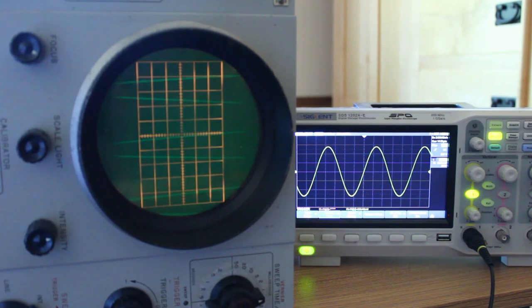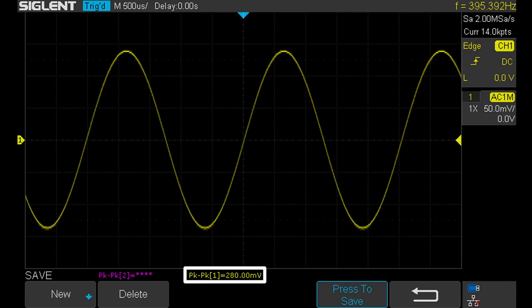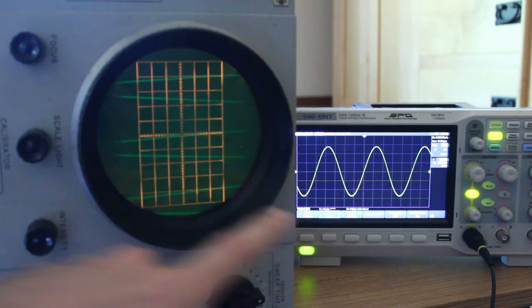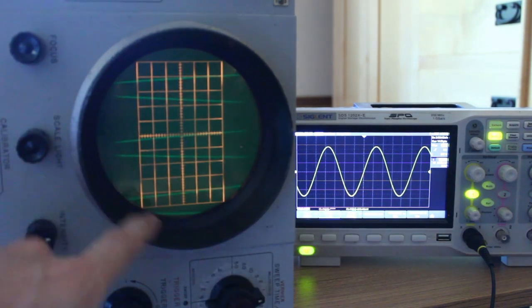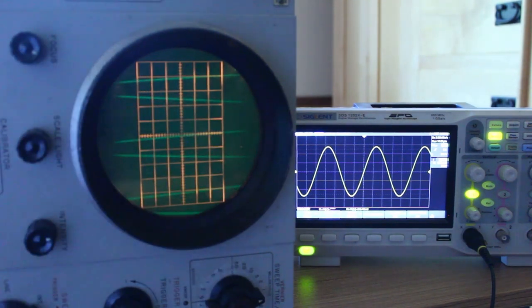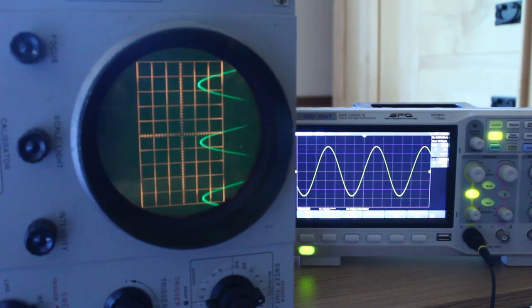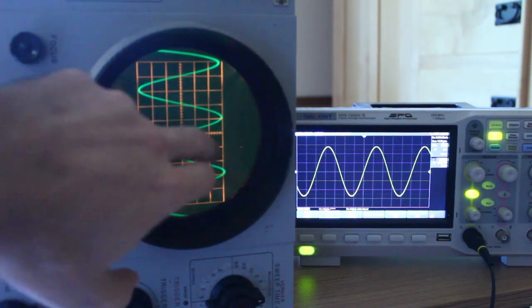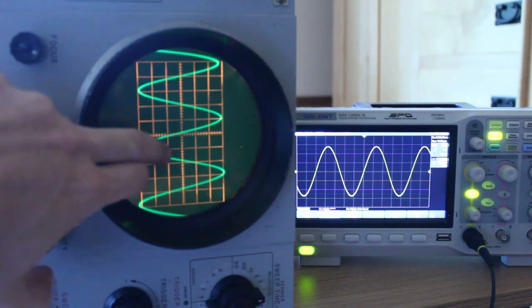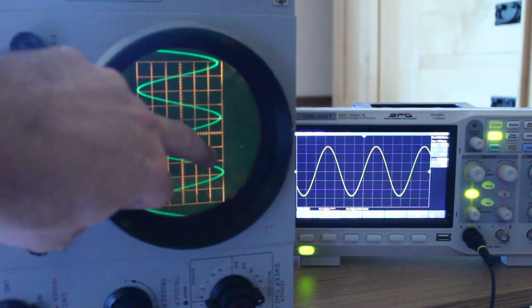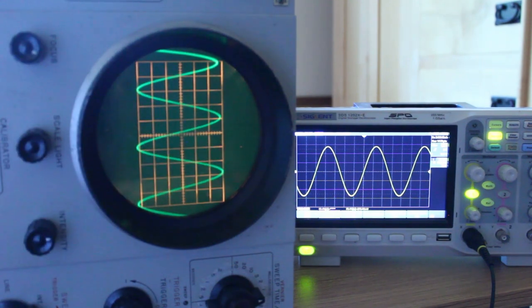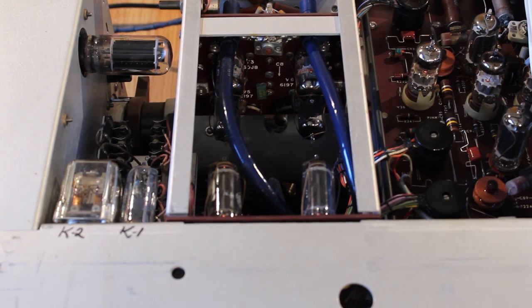So I had to turn the lights off in the room so we could actually see the CRT here. And you can see that we have a 280 millivolts sine wave coming in here. And that's 280 millivolts after the 10x reduction of our probe. But you can see that the sine wave is straight off of the scale. So if we bring this up to 0.2, you can see the sine wave goes pretty much top to bottom. So if we count the centimeters here, we've got 0.2, 0.4, 0.6, 0.8, 1.0, and then 1.2. So we know that the 152B plug-in unit on the bottom is working correctly because we verified that earlier. So the only other thing that could be possibly affecting the vertical amplification should be the main vertical amplifier. So that's where we're going to shift our focus next.